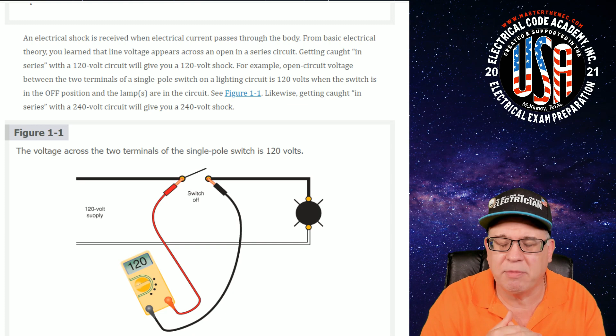No need for it. Now if you have panels, for example, where the lines come into the panel, you'll have barriers now on the line lugs that come in, but you have a main breaker for the most part that kills the bus. So you're working below those live parts. But you still have to use precautions. You still have to be aware of what's going on, and the manufacturers are doing things to try to make you as safe as they can. Again, common sense has still got to always be prevalent when you're working with electricity.